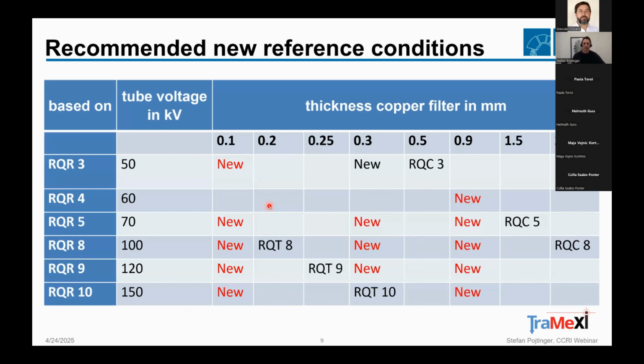Based on comparisons like this, we came up with several proposals we would like to give to IEC for an update for the next revision of the standard. One thing we found was that there's a lack of reference X-ray radiation conditions that cover low or thin copper filters. So our first proposal to IEC is to introduce reference radiation conditions for that. So really thin copper filters, for example, 0.1 millimeter of copper for a 50 kV X-ray tube. That is something we would recommend because this is not covered by the international standard.